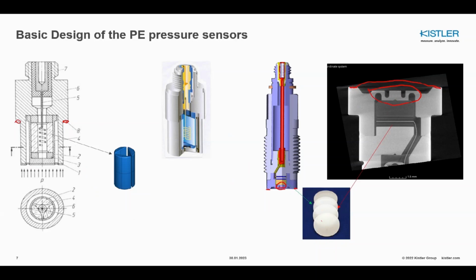Of course, the mounting influences the measuring condition. In the shoulder seal sensor, you can see that the sealing surface is here and the stress goes up, and the crystal part is not influenced by the mounting forces. On the other hand, when here is the pressure, it goes to all the parts, this one and that one, bending in this direction. So you have to count with it and leave enough space here without any particles to allow the sensor to so-called breathe, moving this way and that way. So this is really just another disadvantage of this sensor.